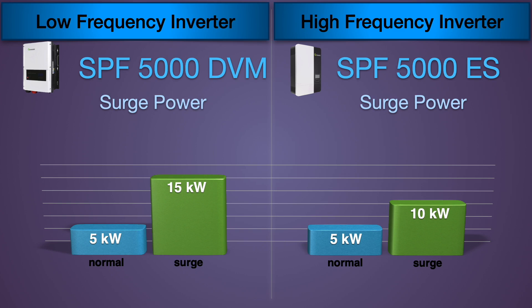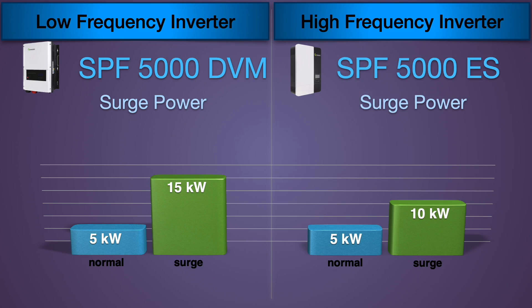So at one point, it was basically considered if you needed to start big motors and so forth, you would go with a low frequency inverter. However, it's not really necessary anymore. You just have to make sure that the high frequency inverter that you're looking at can handle the surges that you are going to throw at it.